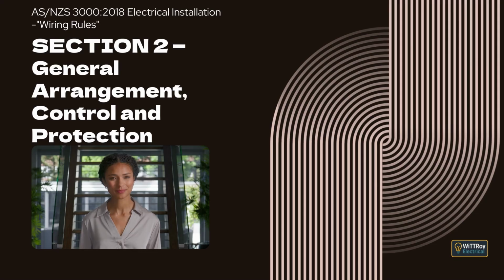Clause 2.10.6 Wiring. Switchboard wiring must be installed so it can withstand the heat and magnetic forces that occur during faults. Where panels need to be moved for maintenance, the wiring must be long enough to allow safe movement, must be held in place to prevent strain, and must be arranged so cables are not crushed behind the panel.